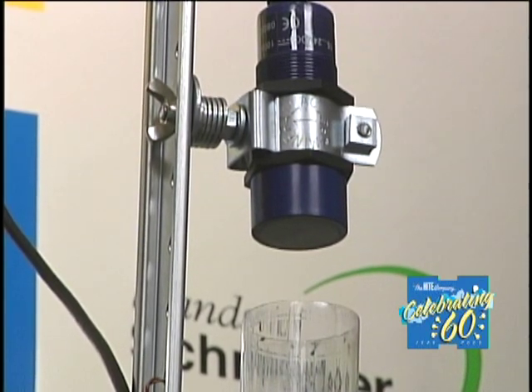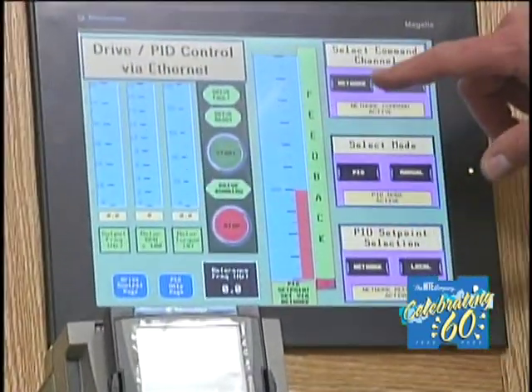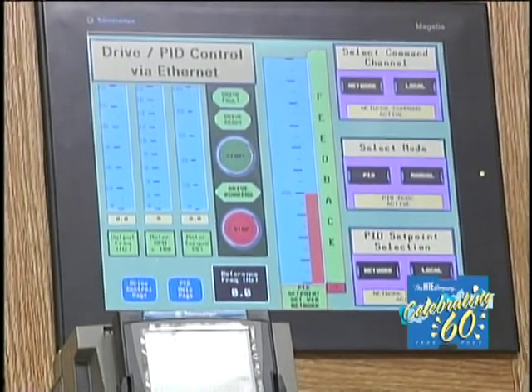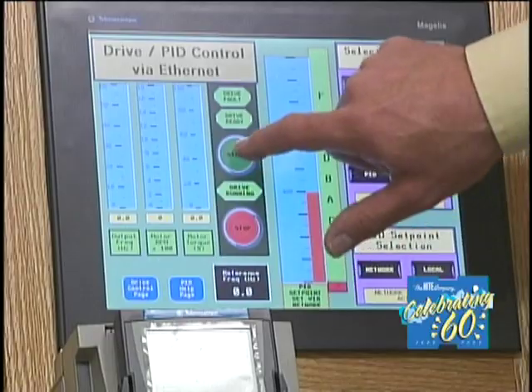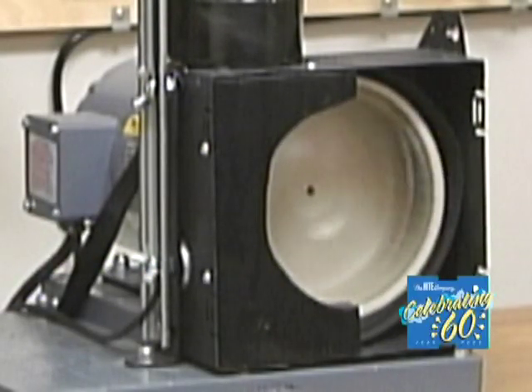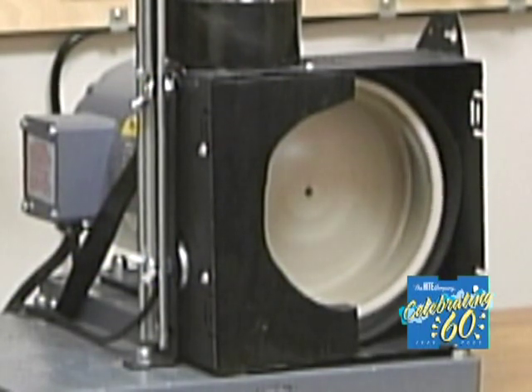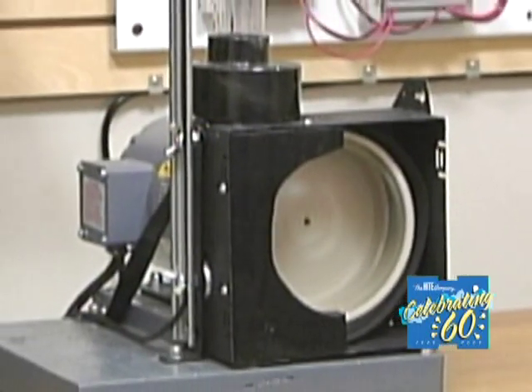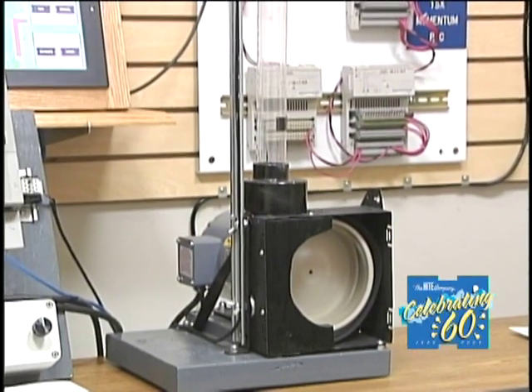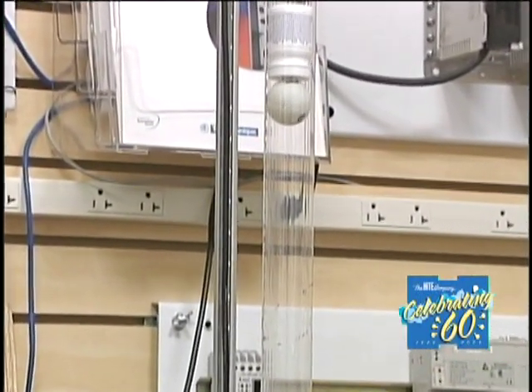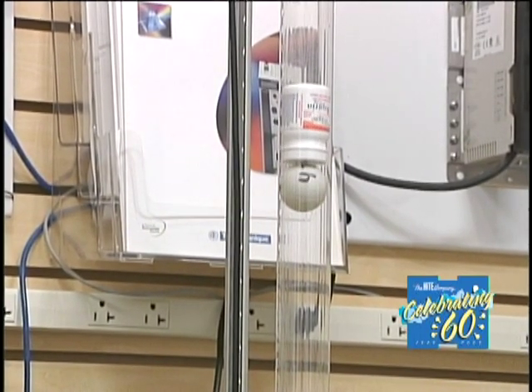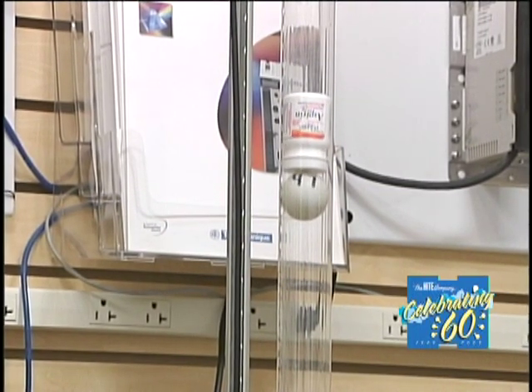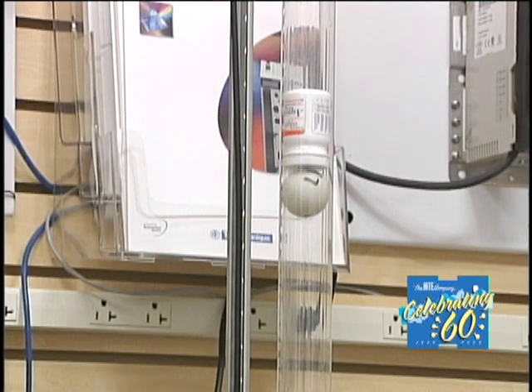That's the equipment list — we'll go into the demonstration. The setpoint is on a scale of 1 to 1000, which is a handy range to work with. Right now the setpoint is set at 400 out of 1000. We'll go ahead and start it. The pill bottle is floating now at about 400. This is actually a very touchy application — the pill bottle takes very little change in speed of that blower to move around, so the PI controller in that drive is pretty busy.